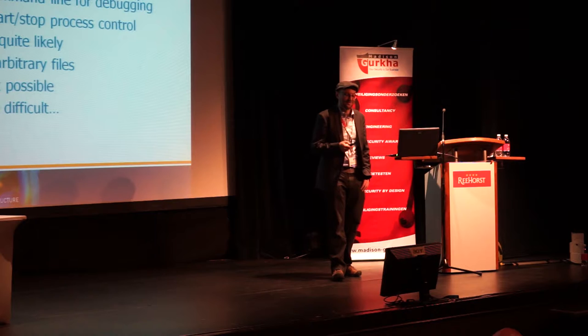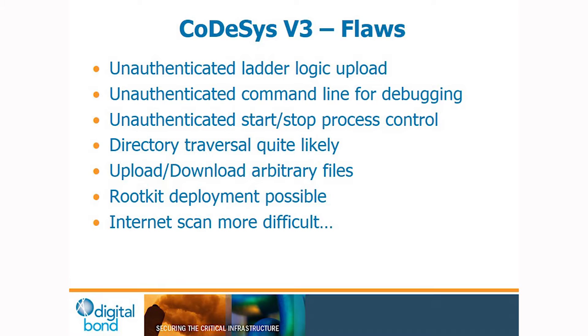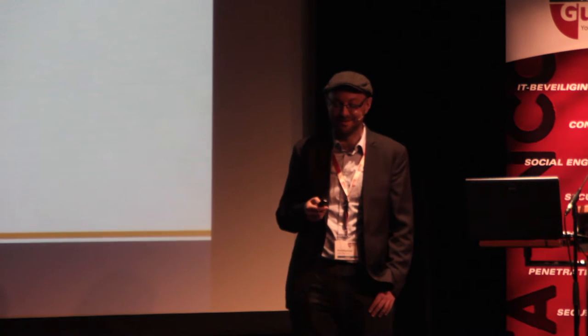CODESYS version 3 has all the same flaws: unauthenticated process control upload and download, an unauthenticated command line, the ability to start and stop process control. Directory traversal is quite likely, and rootkit deployment will probably also work. We did develop a rootkit for version 2 for one PLC but haven't done it for version 3 yet. Scanning for these on the internet turns out to be a lot more difficult.